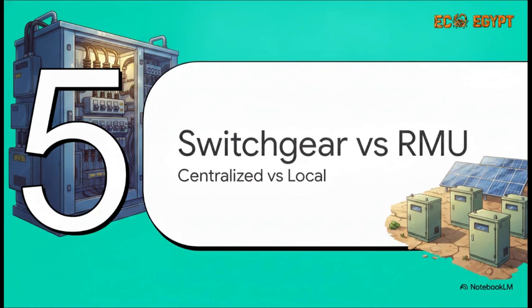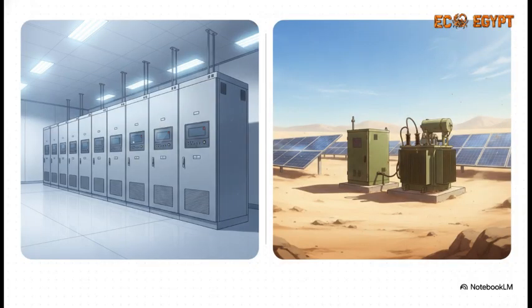Section 5. Switchgear versus the RMU. Centralized versus local. It's absolutely vital to understand the difference between centralized and local setups when looking at the overall plant layout. A standard MV switchgear is a centralized, metal-clad modular lineup. It relies heavily on robust vacuum circuit breakers, or VCBs, to handle multiple high-current feeders right at the main substation. The RMU, or ring main unit, on the other hand, serves a totally different purpose. It's a compact, fully sealed enclosure that is insulated with SF6 gas. You'll generally find these RMUs sitting locally out in the PV blocks, right at the transformer terminals. They provide local load isolation and loop continuity all the way out there in the dusty, high-temperature field.